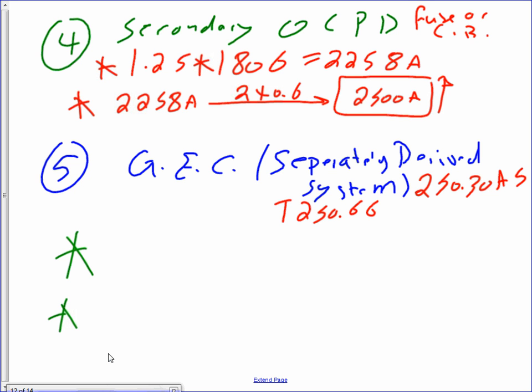Would it make a difference if it's a circuit breaker or fuse here? No, on the secondary side it doesn't make a difference. On the primary side, the high voltage, you have to decide. If you put a circuit breaker on the primary side, guys, you have to multiply by 6. If you put a fuse, you have to multiply by 3. Major difference. That's the difference between having a 600 amp fuse or a 300 amp fuse, or a 600 amp circuit breaker or a 300 amp circuit breaker.